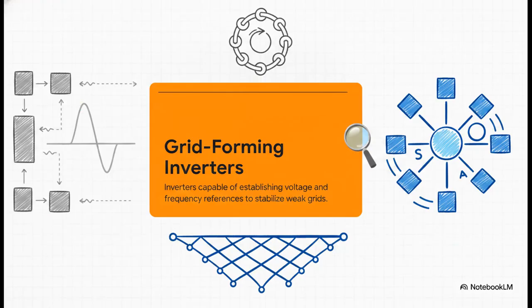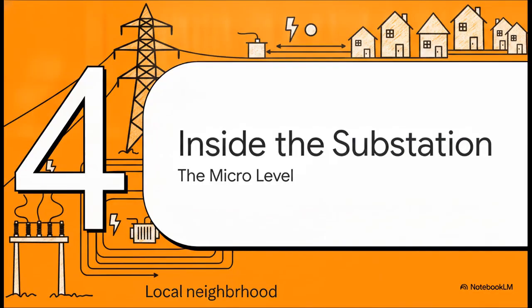Let's focus on grid-forming inverters for a second because they're a total game changer. Older renewable setups used grid-following inverters, which basically just passively matched whatever frequency the grid told them to. But grid-forming inverters are proactive. They actively build the grid stability by establishing their own voltage and frequency references. They act as a digital safety net, perfectly emulating the behavior of a synchronous generator, but without a single moving part. All right, Section 4.